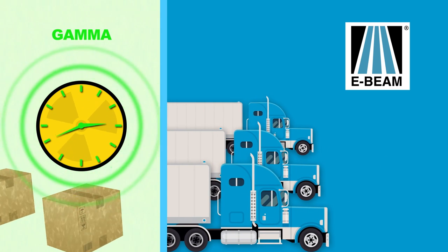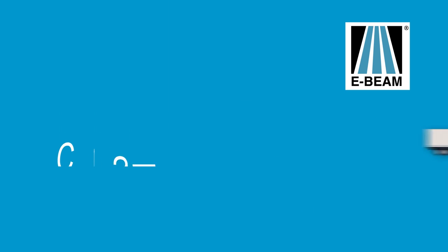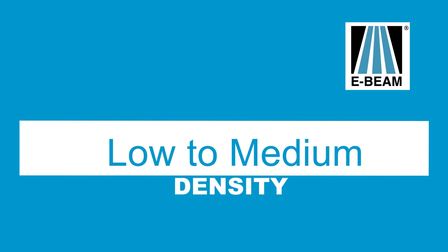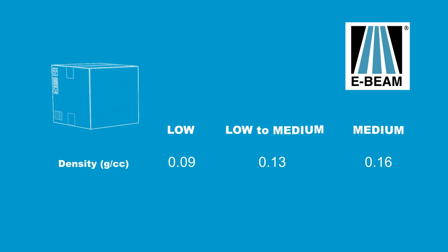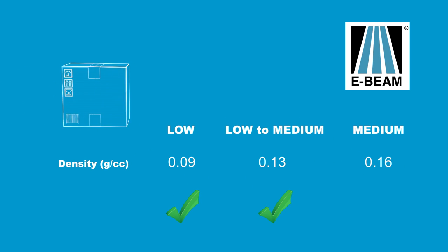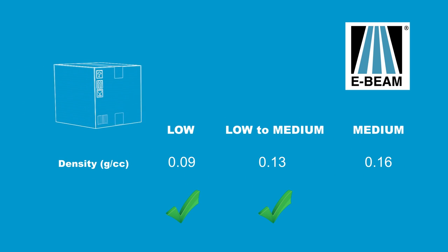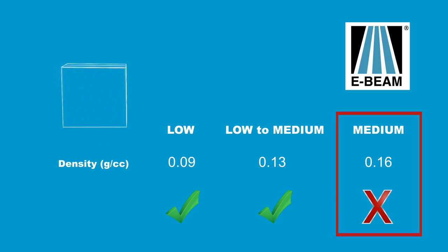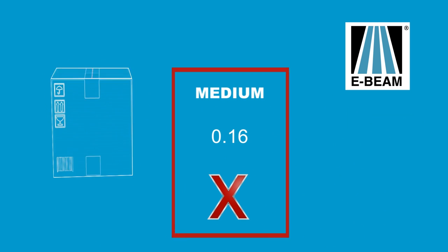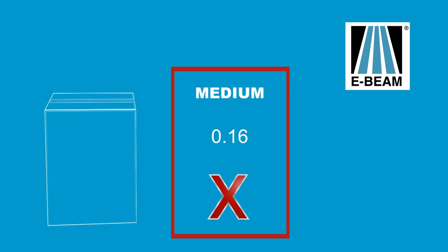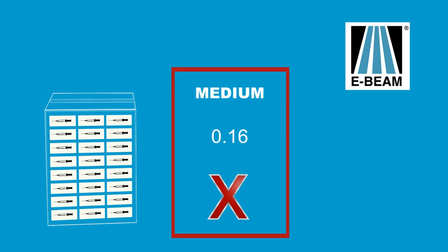E-beam services provides the most cost-effective radiation sterilization for low to medium density medical devices. For example, tall boxes with low or low to medium density could be successfully sterilized. However, a tall medium density box might not receive good enough dose distribution within the box.